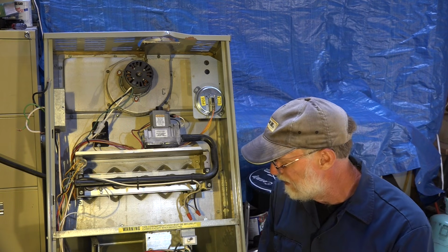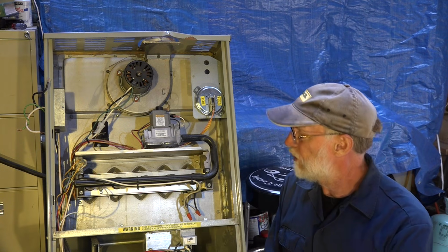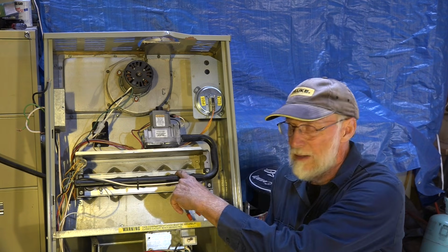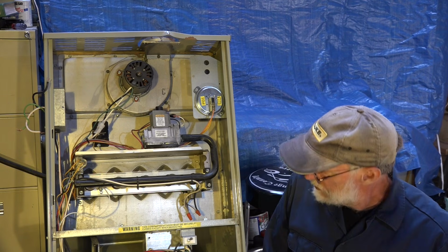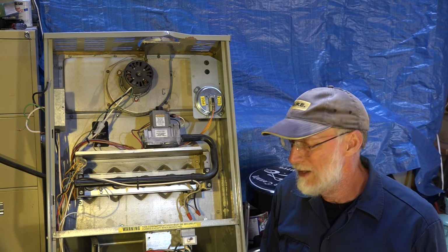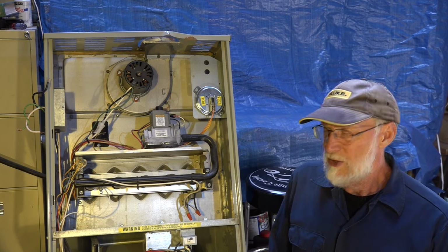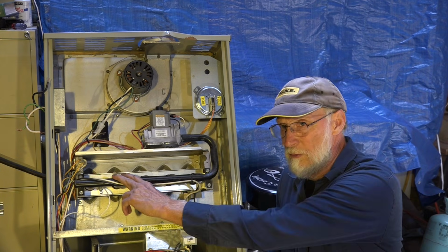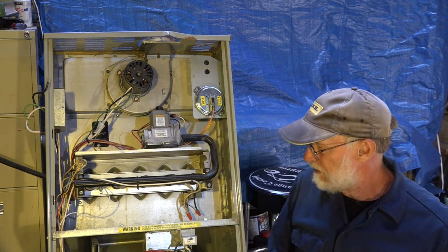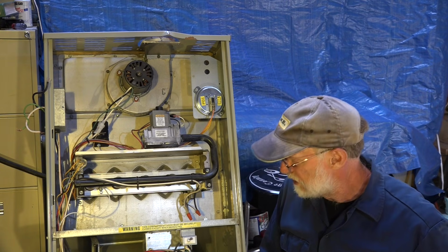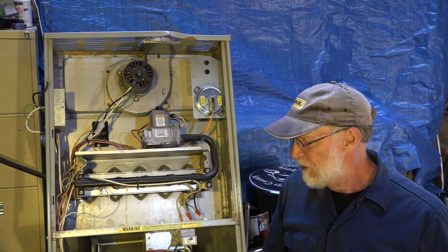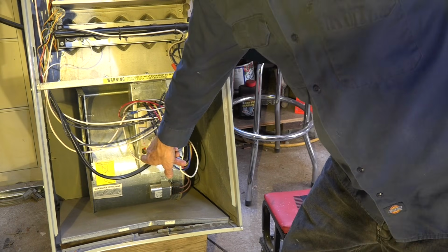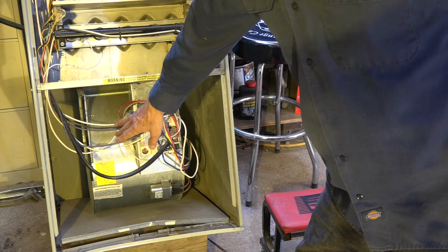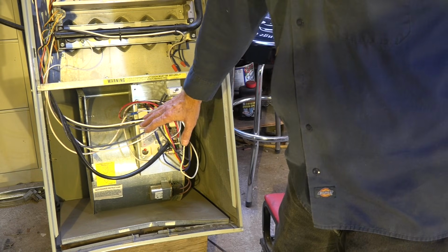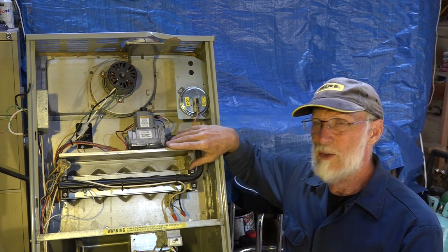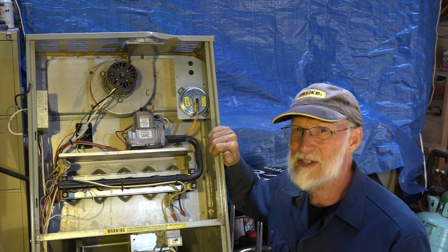This is a mid-90s 80% furnace. The burners are right here, and the heat exchanger is behind there. In order to check to see if there's cracks in the heat exchanger, there's a couple of ways you can do it. One, you can remove all the burners and inspect either with a camera or just a flashlight. Or you can go down to the blower, pull the blower out and check there. The reason I told you about these two different places, is they're not real simple to tell, are they?